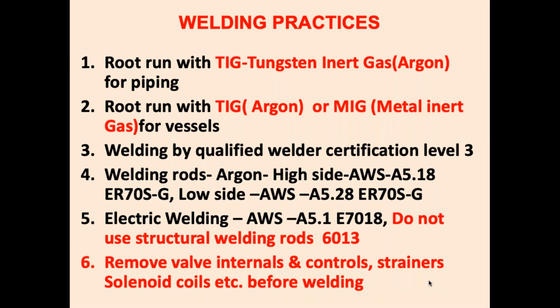The next, welding practices. A lot of people use maybe the correct steel for the piping and for the shell, but doing correct welding is very, very important. The root run should be done with TIG welding, that is tungsten inert gas welding, because then contamination will not enter into the pipeline and your internals will remain clean. Root run with TIG, or that is argon, or with MIG gas for vessels. Welding by a qualified, certified welder, not by any welder. Very, very important. Certification and qualification is very, very important.